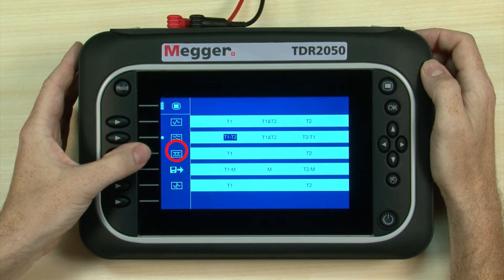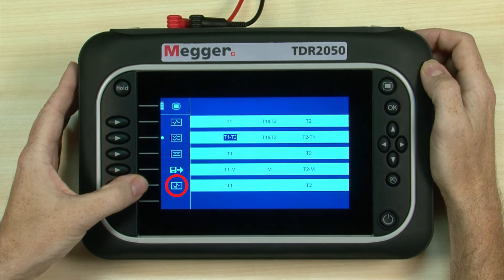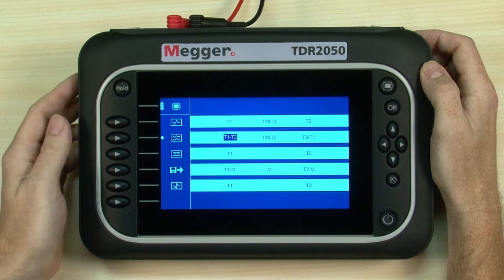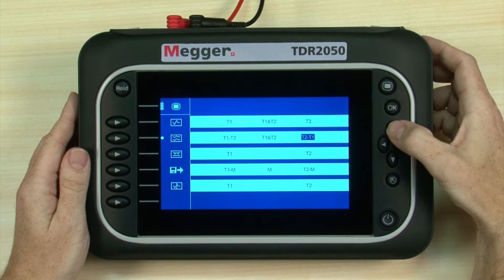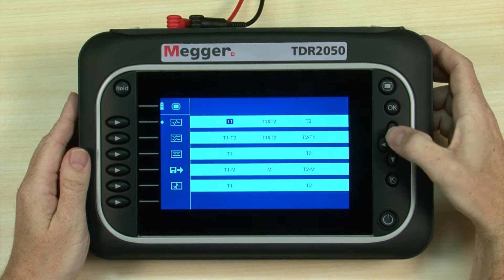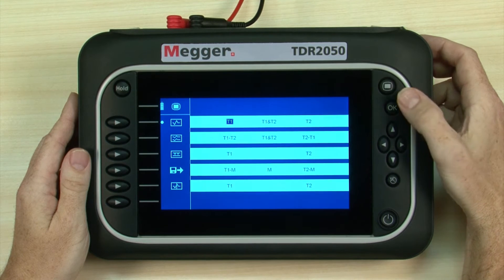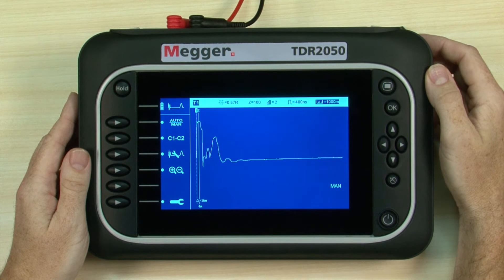And we can examine crosstalk, view memorized traces, or set up for an intermittent fault test. We have a single cable to test, so we'll choose a single input mode. Using the navigation buttons to navigate left, right, up and down, we highlight T1 from the full screen trace mode section. The OK button is used to select the highlighted action or to accept entered text or information.